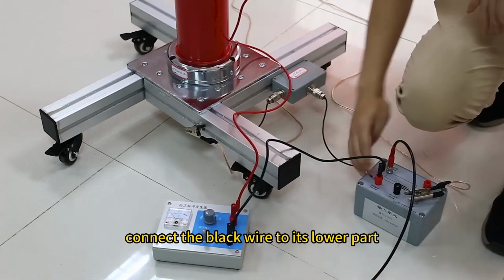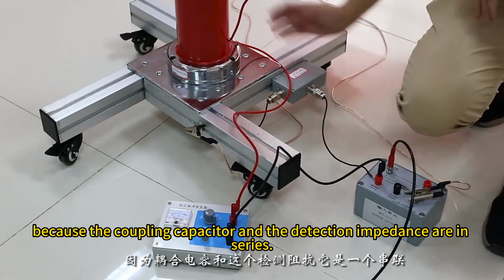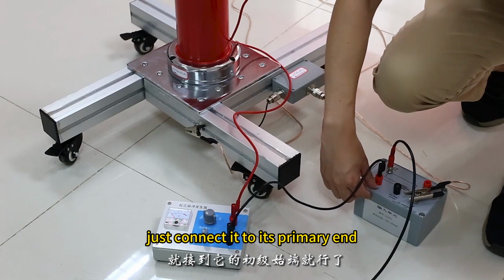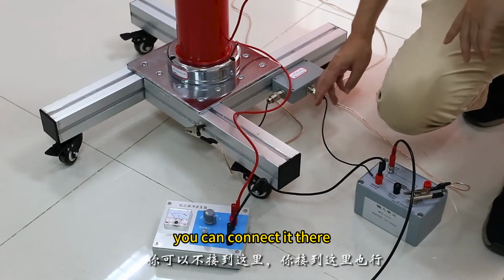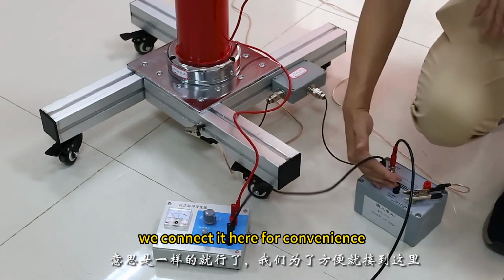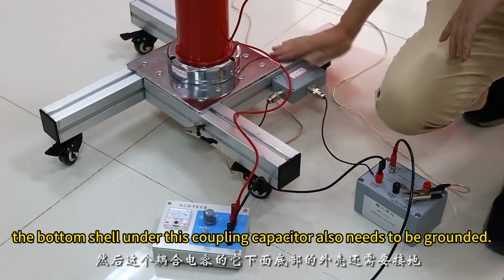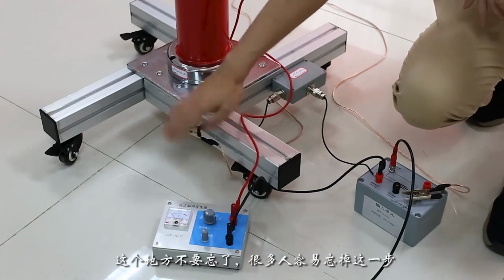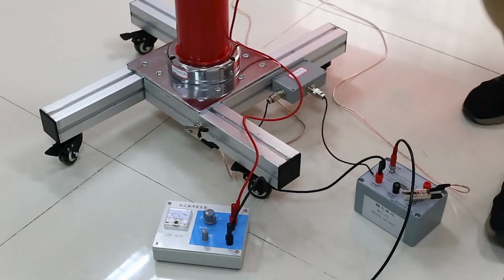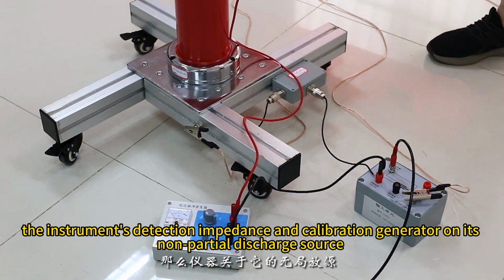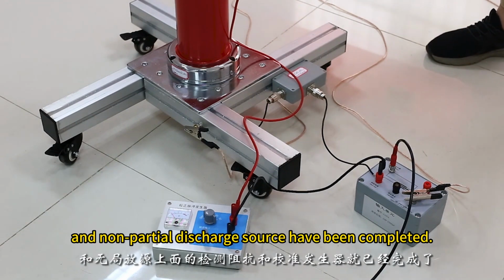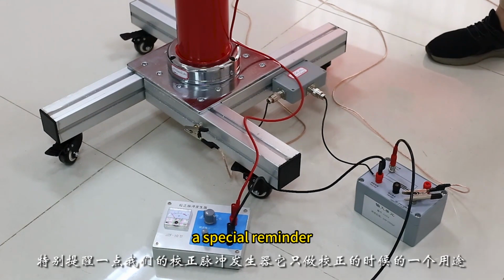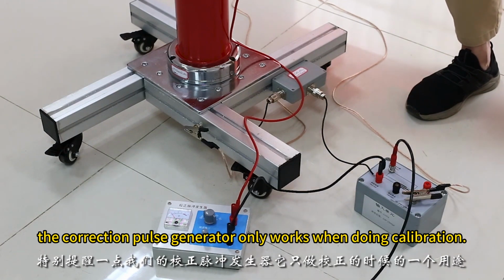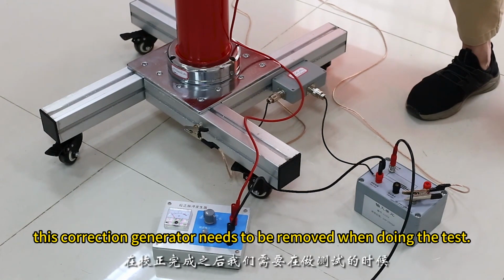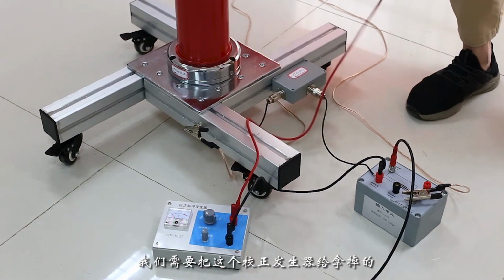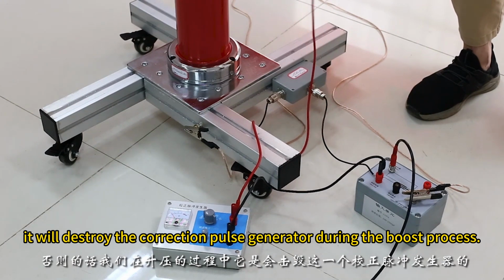Connect the black wire to its lower part, because the coupling capacitor and the detection impedance are in series. Just connect it to its primary end. If you don't connect it here, you can connect it there. We connect it here for convenience. The bottom shell under this coupling capacitor also needs to be grounded. Don't forget this, many people tend to forget this step. The instrument's detection impedance and calibration generator on its non-partial discharge source have been completed. A special reminder, the correction pulse generator only works when doing calibration. After the calibration is completed, this correction generator needs to be removed when doing the test. Otherwise, it will destroy the correction pulse generator during the boost process.